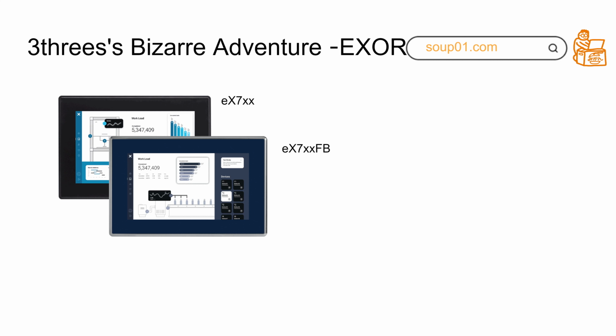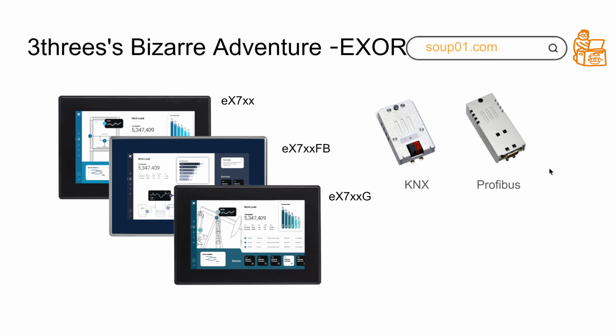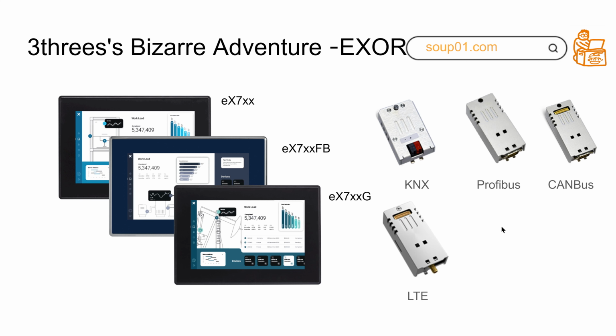They are also very resistant to water, and there are so many features that I cannot explain all of them in this slide. Then they also have the EX7 with a G letter, which means the outdoor models. For these models, they can use plugins installed behind the panel. The front of the panel is IP67 and the other side is IP20. You can install a KNX module, Profibus module, CAN bus module, LTE modules, and digital input-output or analog modules.